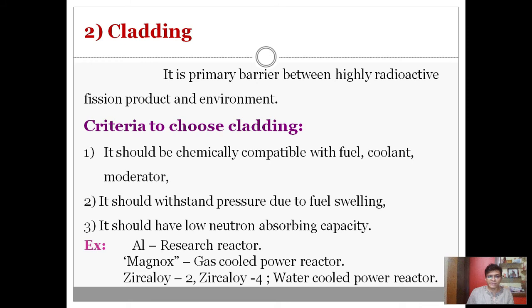The cladding material is chosen depending on the type of nuclear reactor. Aluminum is used in research reactors. Magnox alloy — an alloy of magnesium, aluminum, and beryllium — is used in gas-cooled power reactors. In water-cooled power reactors, Zircaloy-2 or Zircaloy-4 is used. Zircaloy-2 is an alloy of zirconium, tin, iron, chromium, and nickel, containing 0.15% iron, while Zircaloy-4 contains around 0.2% iron.